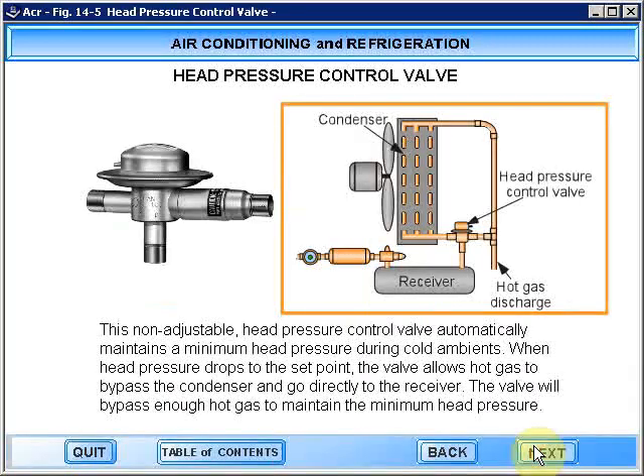This non-adjustable head pressure control valve automatically maintains a minimum head pressure during cold ambients. When head pressure drops to the set point, the valve allows hot gas to bypass the condenser and go directly to the receiver. The valve will bypass enough hot gas to maintain the minimum head pressure.